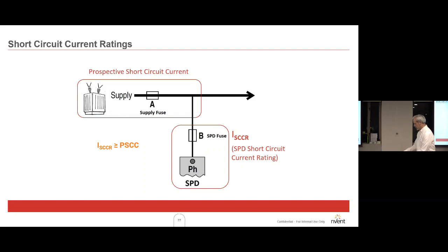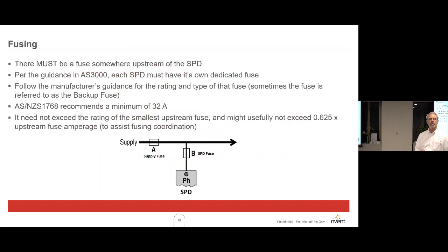These particular products have larger terminals, and you can actually use up to 315 amps protection on a 25 kA fault rated switchboard. It may be desirable to have the protection in there anyway for convenience, so you can actually work on that circuit. But that's just saying what I just said.